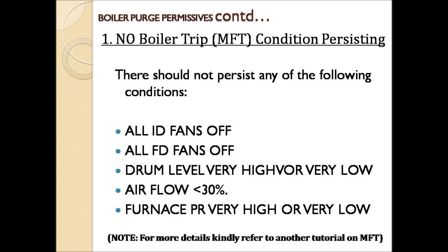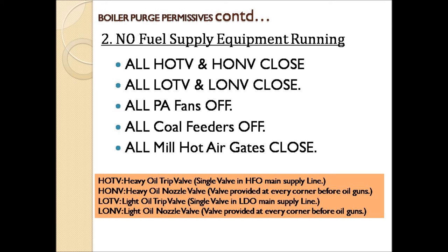For any additional information regarding MFT, kindly refer to my other tutorial on Master Fuel Trip. The second boiler purge permissive is no fuel supply equipment should be running. As already discussed, the main purpose of boiler purging is to remove unburnt fuel from the furnace, so any fuel supply equipment running or any fuel supply valve in open condition is not desirable.